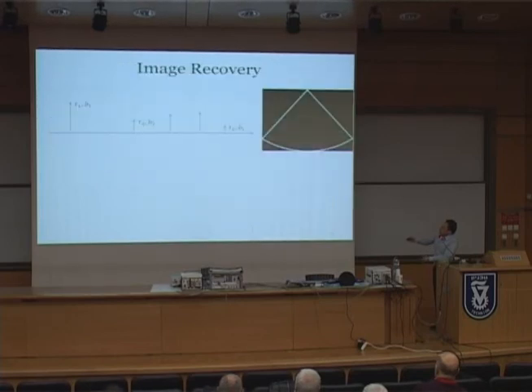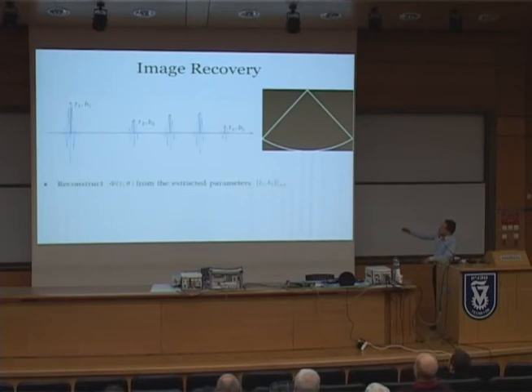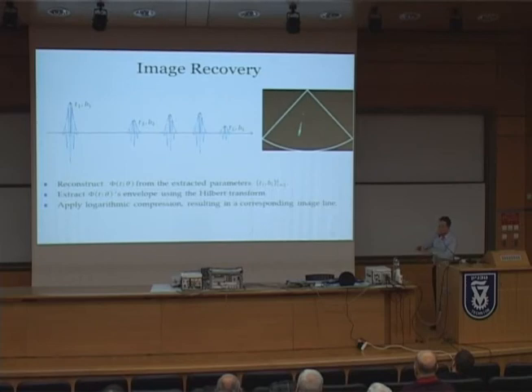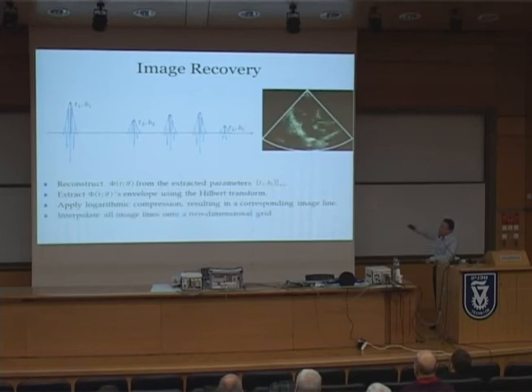The main idea is that we have the recovered delays and amplitudes. We have a known-shape pulse which we place at each delay with the corresponding amplitude. We then proceed with standard ultrasound imaging procedures: extracting the envelope of the signal using the Hilbert transform, applying logarithmic compression to allow showing weak targets next to strong targets on the same image plane, and rendering the image from multiple scanlines — typically 120 scanlines for a cardiac example spanning 60 degrees.